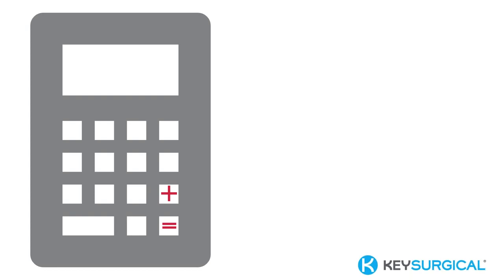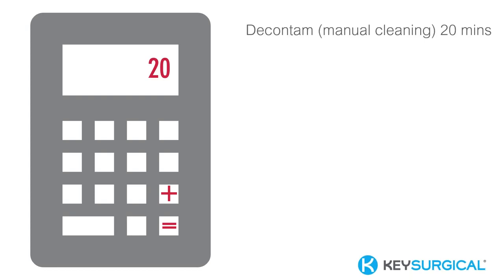But what does it look like in time? I broke down each step in the instrument set cycle in time. So once those items get down to decontam, manual cleaning takes about 20 minutes. And this is, I'm talking like a veteran, well knowing the instrument sets that are coming down and understanding how flow works. Next up, we have the mechanical cycle that can take anywhere from 39 minutes to whatever your mechanical washers need. Eye instruments can take up to 70 minutes in a mechanical cycle. So it all depends on what instruments you're reprocessing.